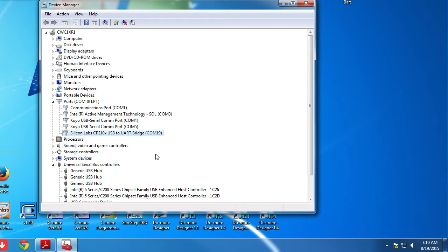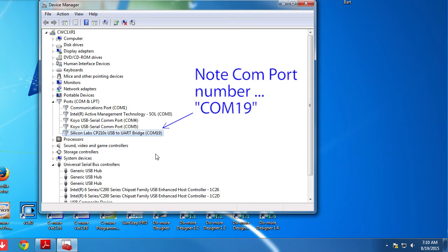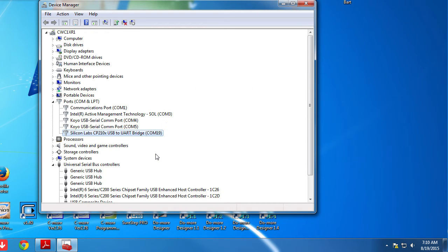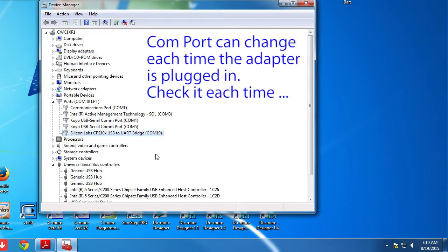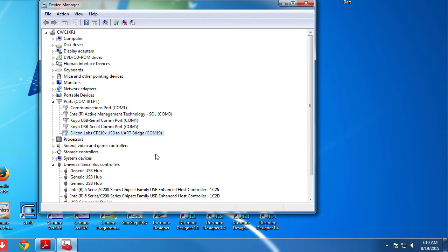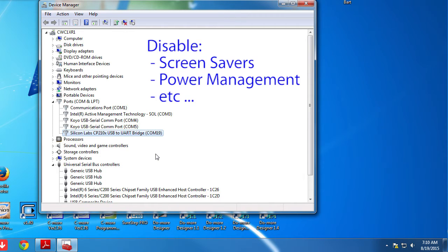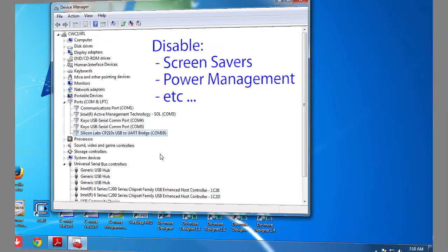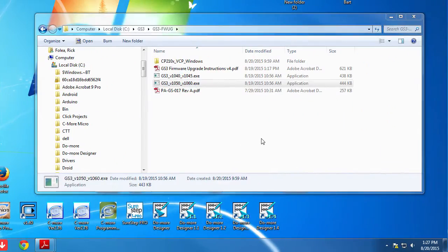Before doing that, go to your device manager and note which COM port the firmware upgrade adapter is connected to. We'll need that in just a minute. It's important to remember that this COM port assignment can change every time you reconnect the USB adapter so check it each time you use it. If you see any warnings here, disconnect the USB cable and reinstall the adapter driver. Be sure to disable any screen savers and power management features that you may have enabled. We don't want anything to interrupt the download process.